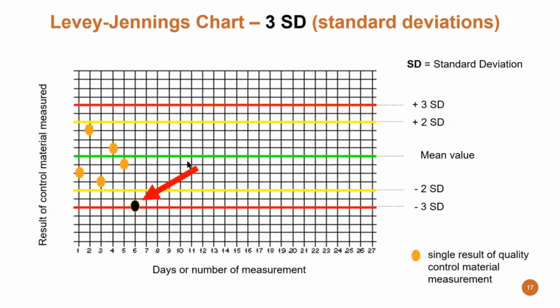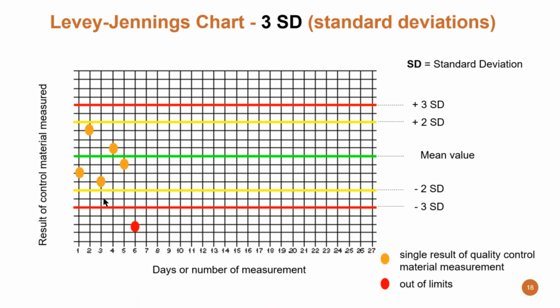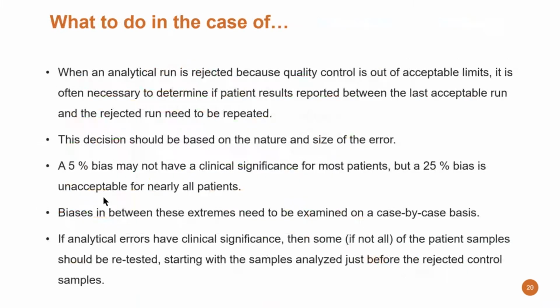Cost increases as well. So now we are focusing on the situation of a measurement which hits the 3SD limit. You can see the arrow and the black point on the Levey-Jennings chart, and here we might have an issue and a problem, and we have to do troubleshooting. That's the topic of today. Just for curiosity, the point is not always on the low side; it could also be outside, up or down. So this is just an example which I'm using to show you how the situation might be. So here we clearly have a value which is outside the 3SD range. And we have to see what we have to do in this case.